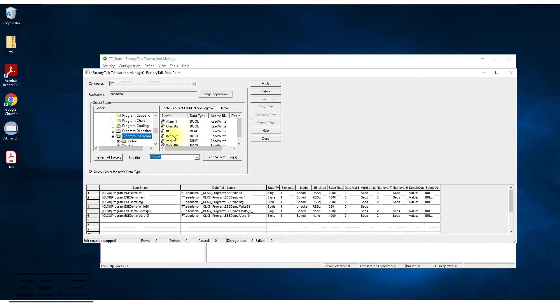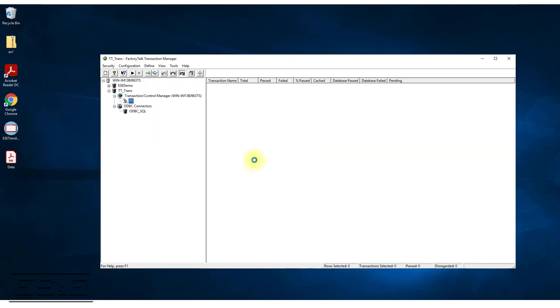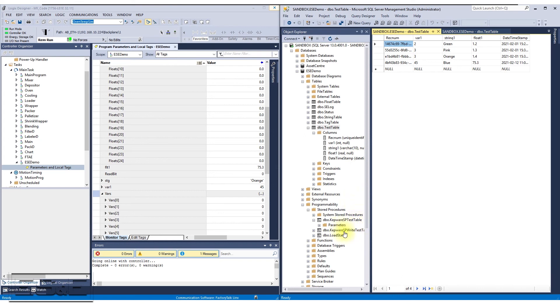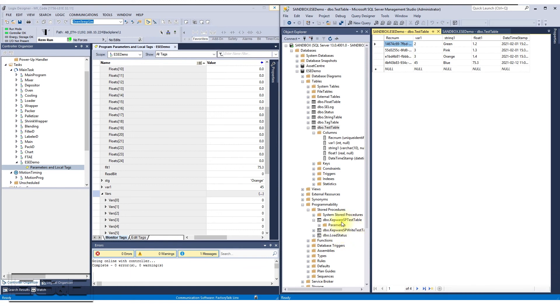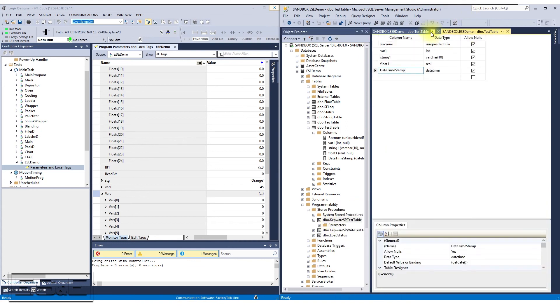The ones we need to define are float_0 (which is an array) and vars_0. Double-click each one to add them. We also need a trigger to tell it to do the read from the database — there's a read bit for that. Remember, if we're going to use something as a trigger, we've got to define it as Unscheduled. Change it to Unscheduled, Apply, and Close. Now those tags have been defined. Let me show you the stored procedure that's in the database.